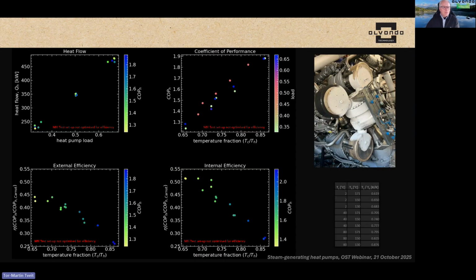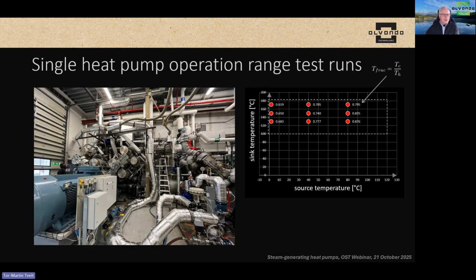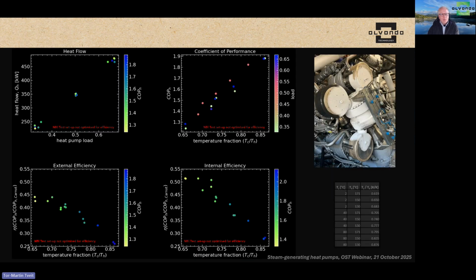What we ended up with is that the coefficient of performance for the heat pump is almost linear with the temperature fraction. I just want to point out that this test setup is not optimized for efficiency, it's more to see how the system behaves. Anyway, we have a quite linear relationship with the temperature fraction. So if you want a rough estimate for a heat pump, calculate the temperature fraction and then use about 50% of the COP.